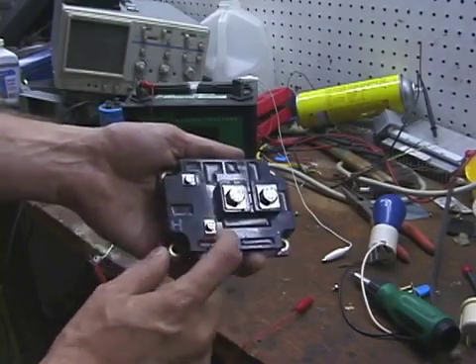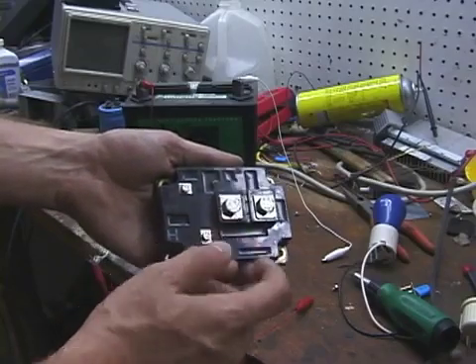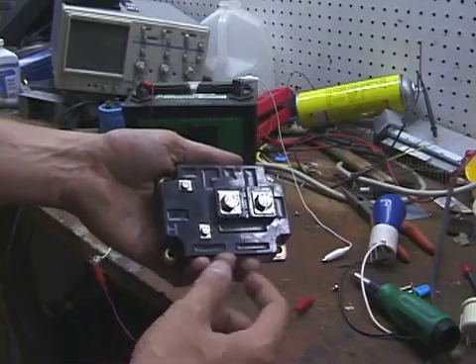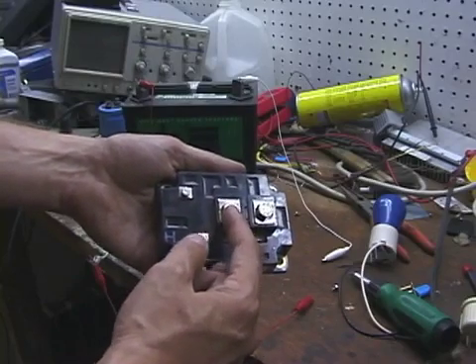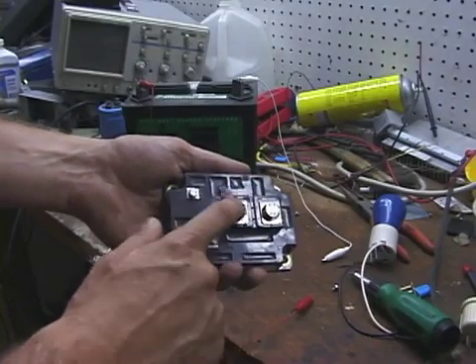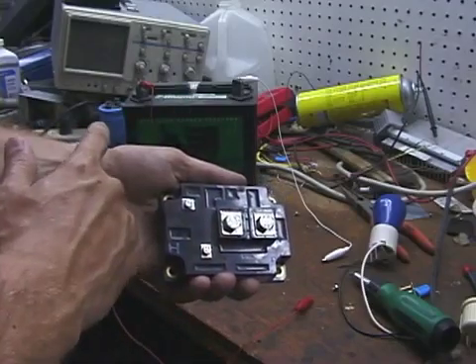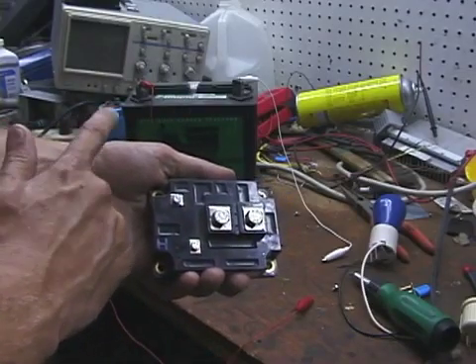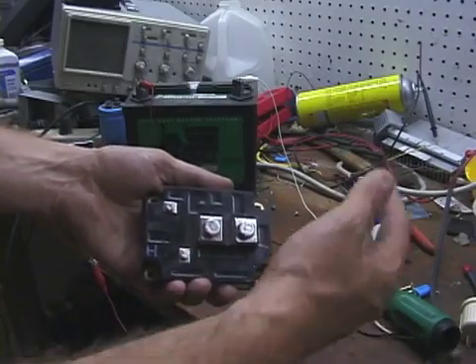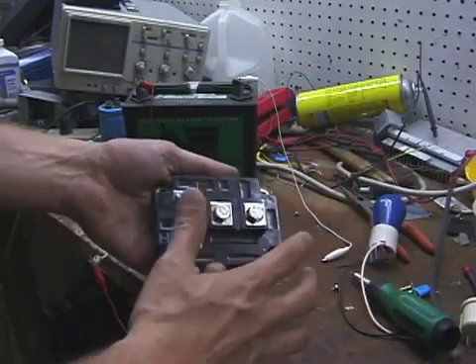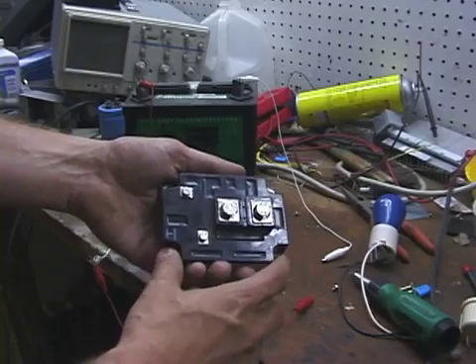The gate is actually where the control voltage is. It actually turns the device on and off, and then the actual power that you want to control goes from emitter to collector. The emitter connects directly to the negative on the DC bus. The collector goes through the load and then on to the positive of the electrical bus.